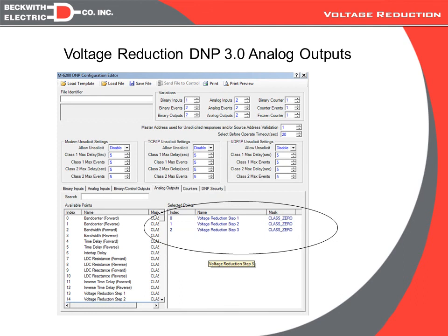We also have analog outputs, which are basically the way we can change the percentages for each of the three levels. So I can write a different percentage to each of the three levels. Now, with all of our analog outputs, if there's a decimal point involved, we do a multiply by 10. So in this case, the percentages are allowed to be from 0.0 to 10.0. So we allow 1 decimal point resolution, so we have to multiply by 10. So for instance, if I wanted a 2.5% reduction, I would write a value of 25 into that particular setting, and then the control, when it received it, would divide it by 10 and come up with the 2.5%.